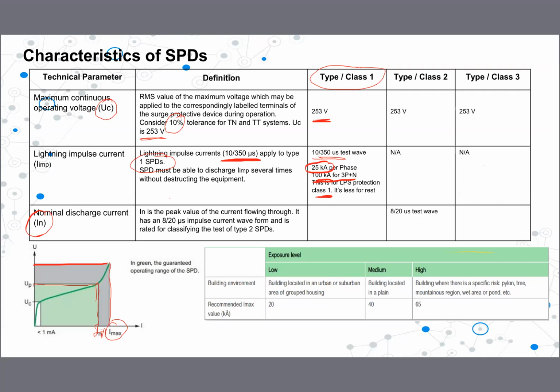So when you decide this current, you need to consider what is also given in this table, right? You need to look at the building environment as well to decide what the IN value is, right? If the building is located in an urban area, there are so many other buildings, so the chance of a direct lightning strike is also very low. Therefore, this value is less. If the building is located in a plain area, again, the probability is high. Therefore, we go for a higher value, right?